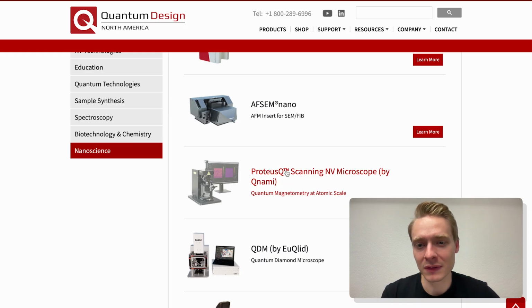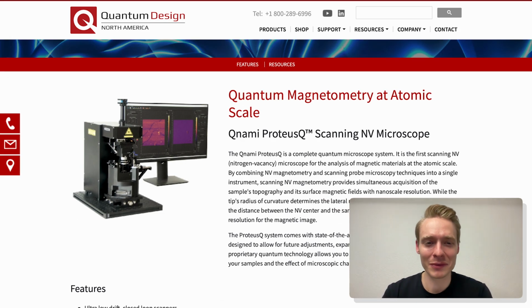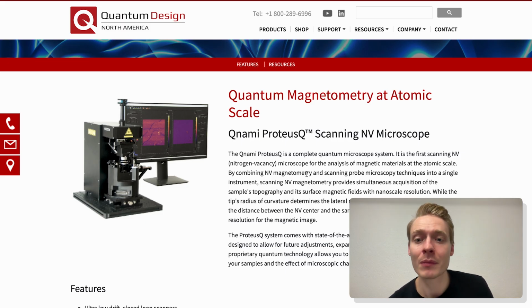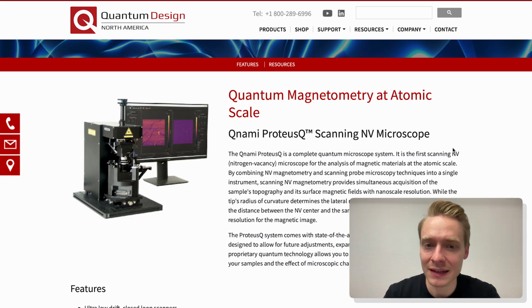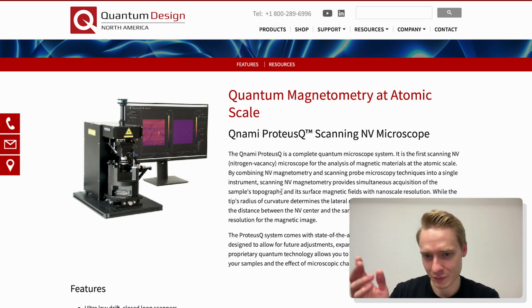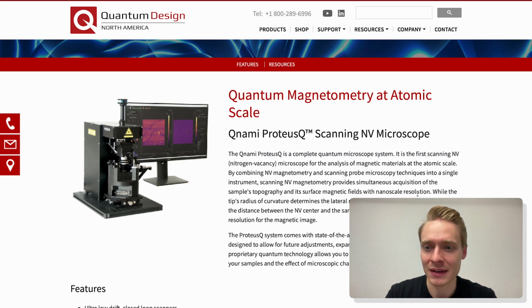So the ProteusQ, a scanning NV microscope by QNAMI, another company that we might want to check out within this series. And I'm now reading from the website: the QNAMI Proteus Q is a complete quantum microscope system. It is the first scanning NV, nitrogen vacancy, microscope for the analysis of magnetic materials at the atomic scale. By combining NV magnetometry and scanning probe microscopy techniques into a single instrument, scanning NV magnetometry provides simultaneous acquisition of the sample's topography, that's what we saw before, right? And its surface magnetic fields with nanoscale resolution, while the tip's radius of curvature determines the lateral resolution of the topography image. It is the distance between the NV center and the sample surface which determines the lateral resolution of the magnetic image.